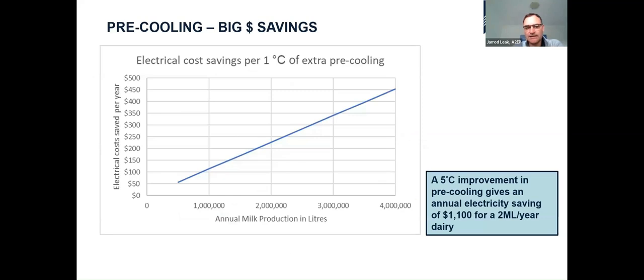Let's give this some context. I think most people would have pre-cooling now, using cooling water from your dam, your river, or whatever other source. And just to let you know how much that does save, if we take an example, going from 2 million litres per annum, if you take that up to the line there and bring that across, it's about $225 per year per degree of improvement for your pre-cooling. Gab's going to take us through what that means to get a good result.